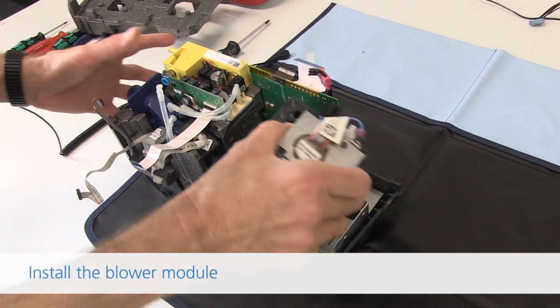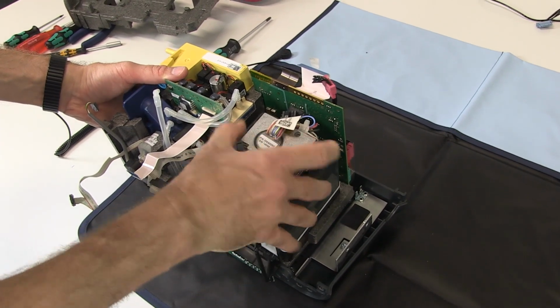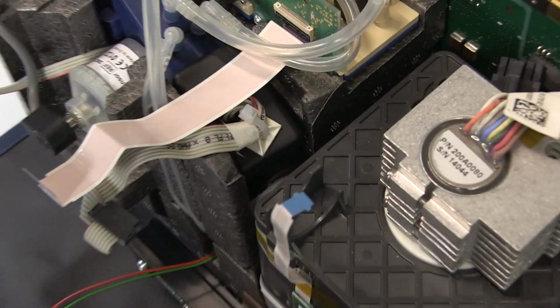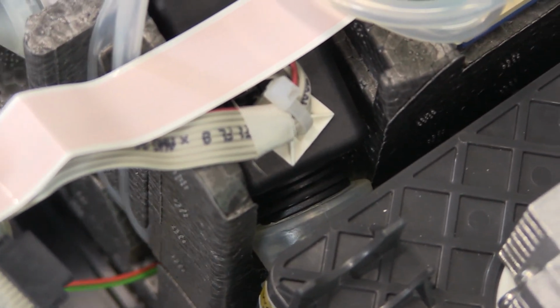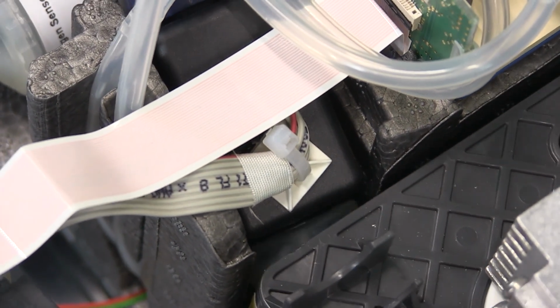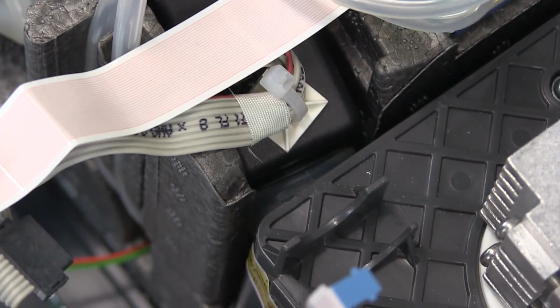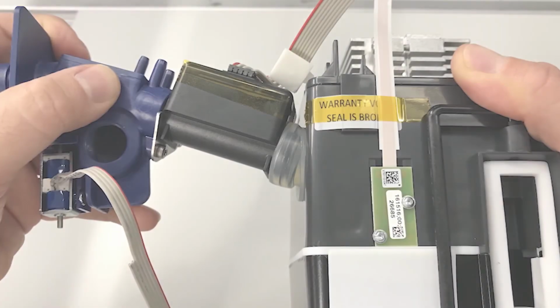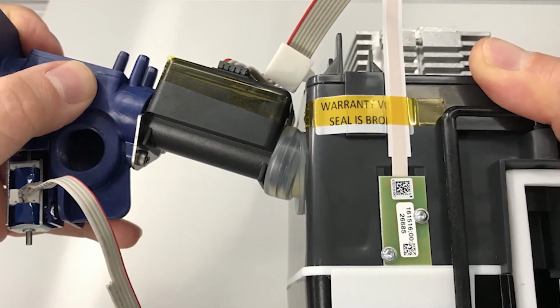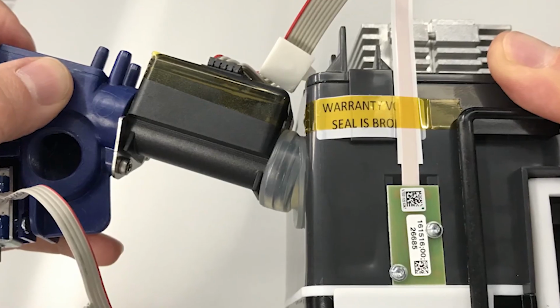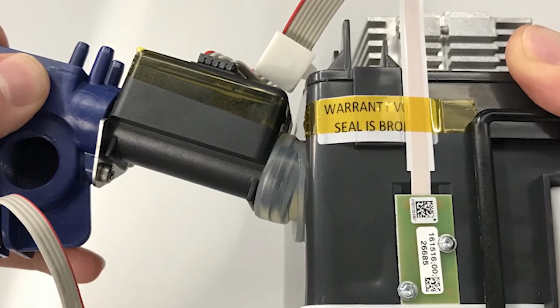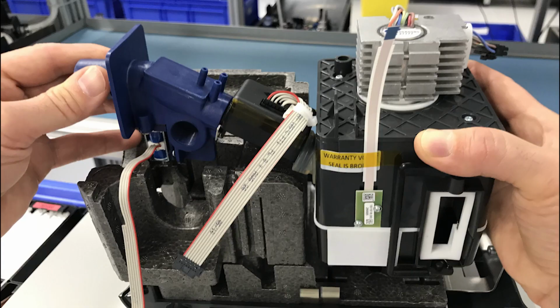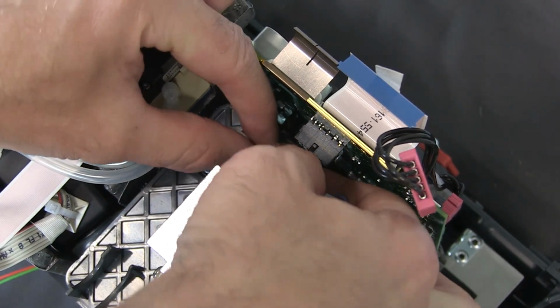Install the blower module. Make sure that the blower module tube is correctly connected to the flow sensor. Recent experience has shown that it is better to connect the check valve assembly with flow sensor to the blower module before you install the sub-assembly. Installing these components together creates a better connection between the flow sensor port and the blower module tube. Connect the blower module cable to the driver board.